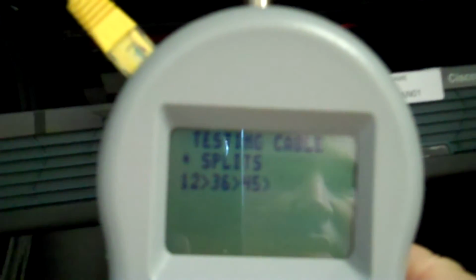So this is testing for data, testing for splits, and doing some speed testing. The whole test runs for about 20 to 22 seconds. If it doesn't find any problems, it'll tell you to take the probe and put it on the far end. When this finishes, it'll say on the screen: plug in probe at far end of cable.